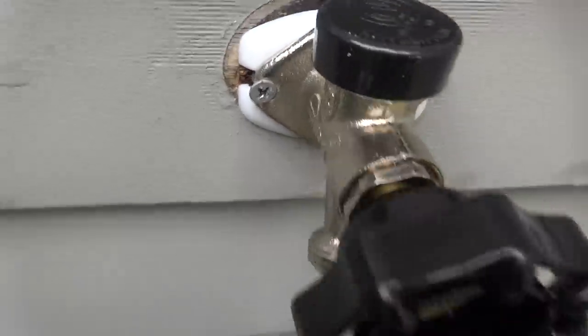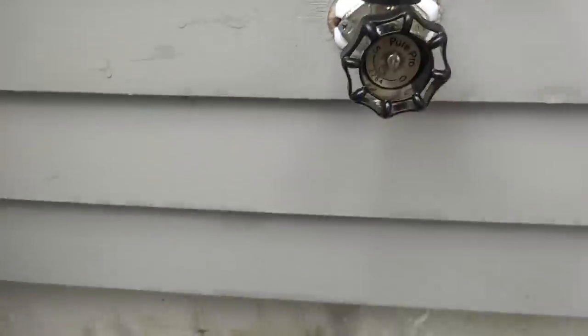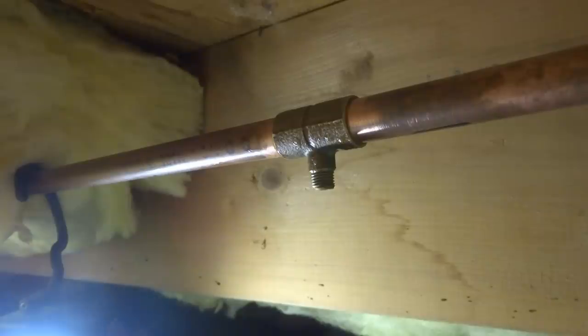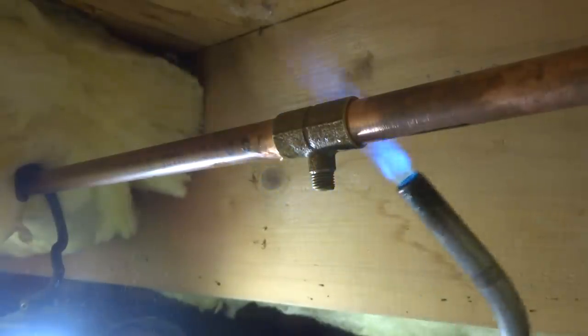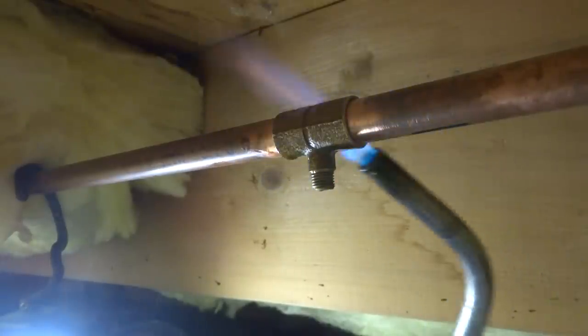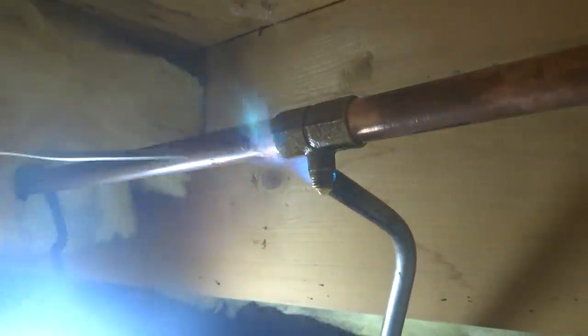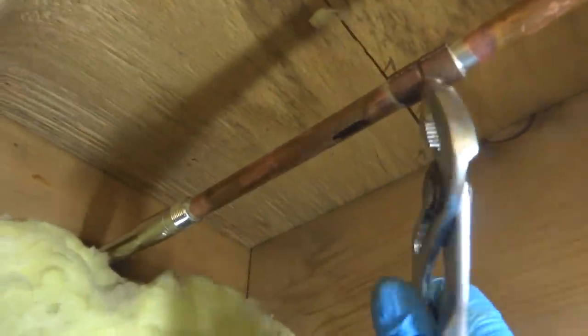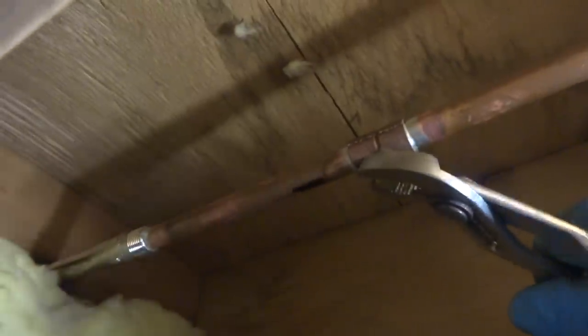That's fine — I came in here, fitted this in, and I just have to go outside, screw it in, level it off, and then solder this end. There are a couple of screws we can shut with — since we've got the bleeder inside, it's gonna go in, solder the inside, put the cap on, and I'll be done. That little bleeder is good to put in there so it doesn't build up pressure.